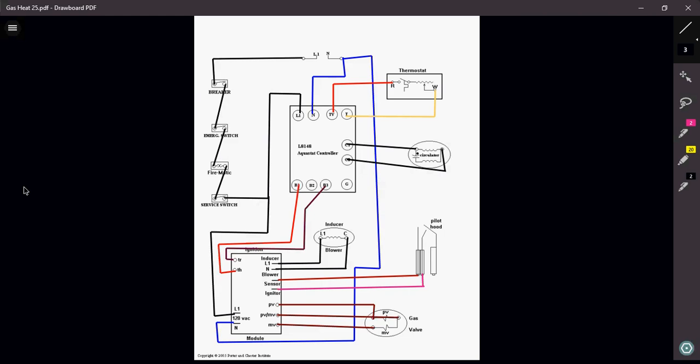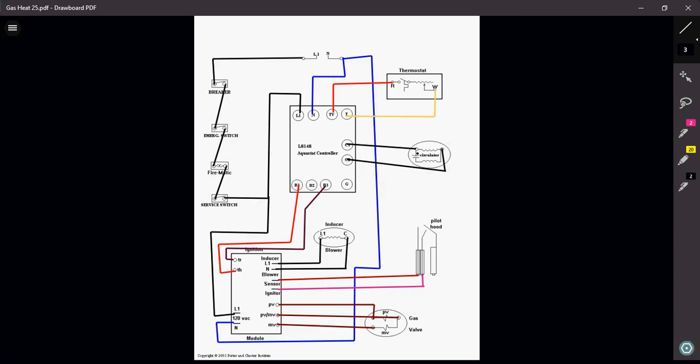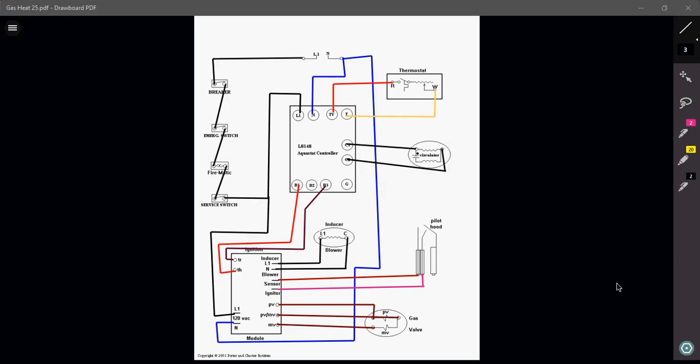Once the boiler starts to heat up at approximately 160 degrees or so, my circulator will then turn on, delivering my hot water to my space so that I can have some heating. And that's how you wire an L8148 Aquastat with an ignition module and inducer blower.